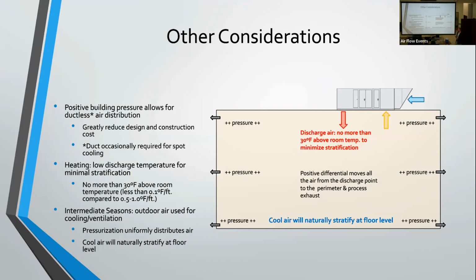When we're looking at heating, typically you want to see your discharge temperatures no more than about 30 degrees above your room temperatures. What happens when you exceed that 30-degree differential is a lot of times, even though you're pressurizing that space and pushing that air outward, that hot air is still more buoyant than the room air. So it wants to float upwards and still stratify a little bit. If you can maintain that 30-degree differential or less, you'll probably see about 0.1 degrees of temperature differential per foot of height in your space.